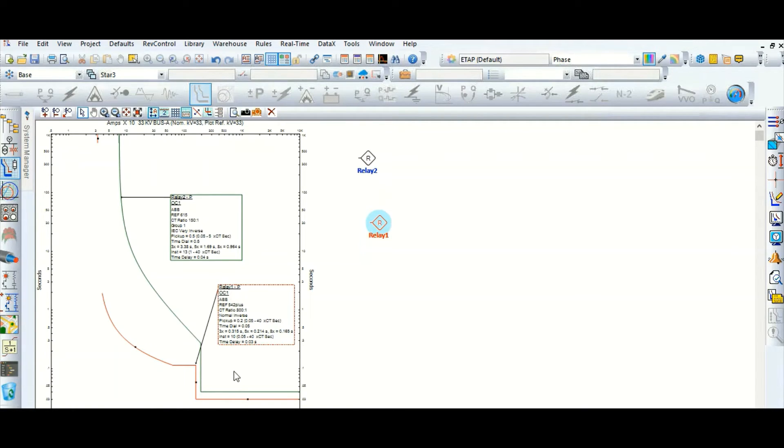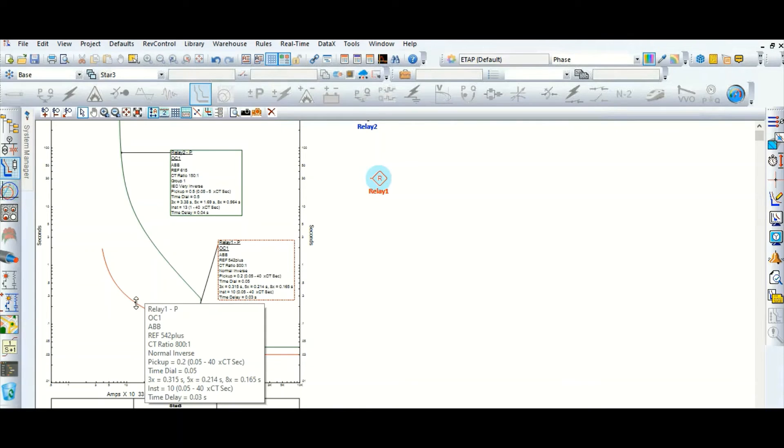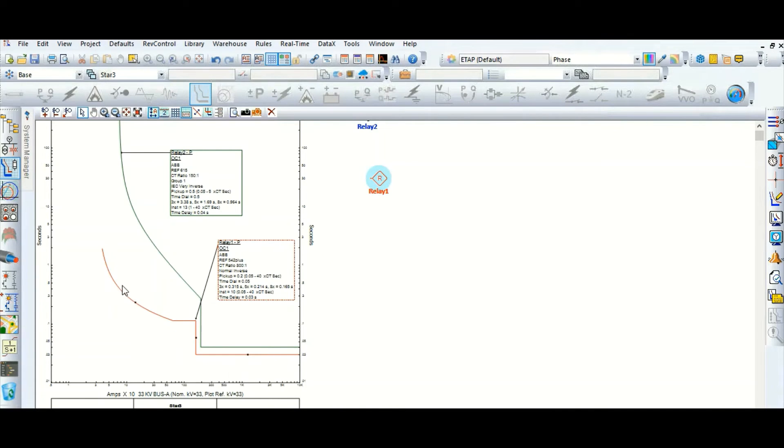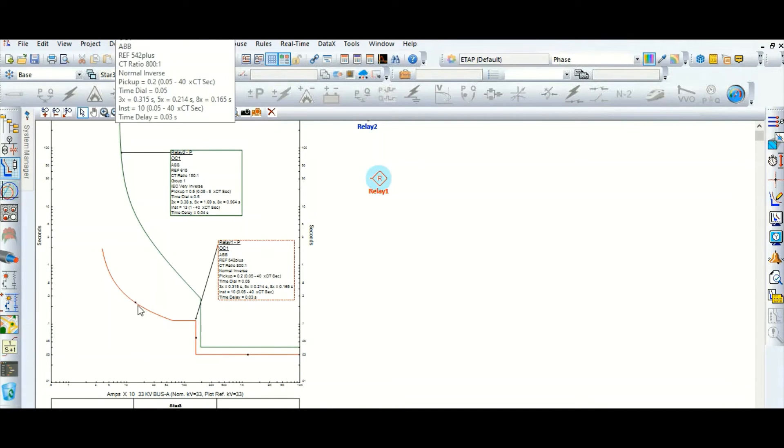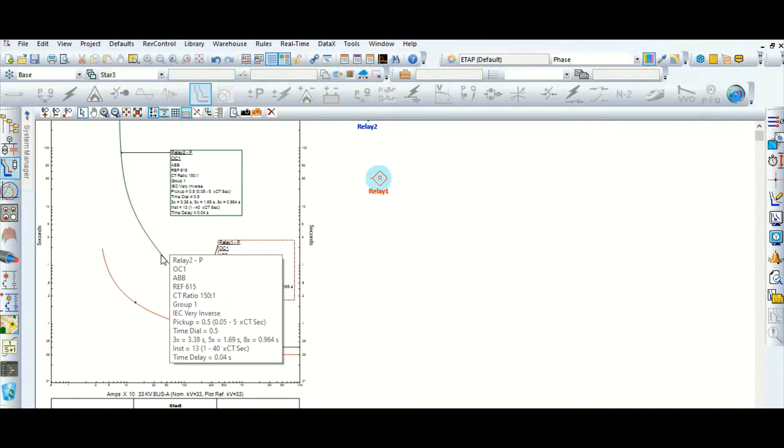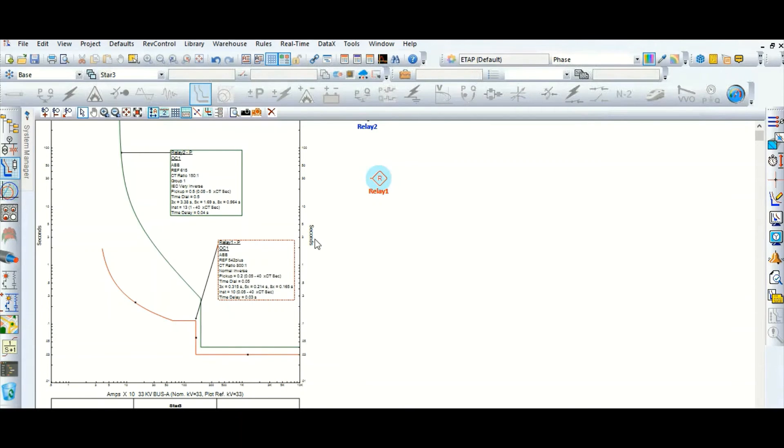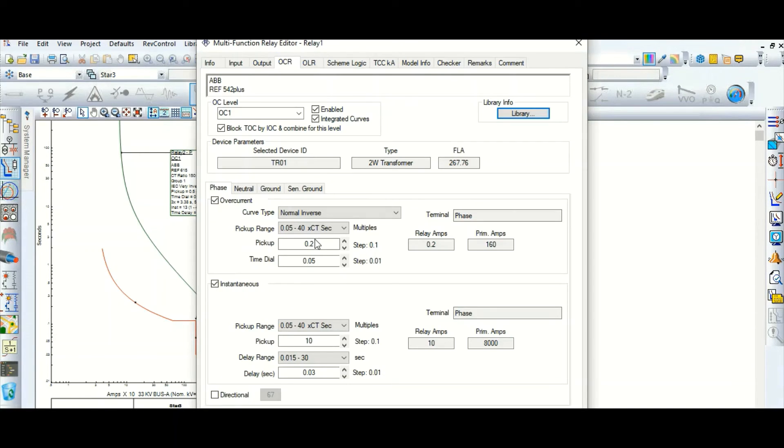But now the question will come, how much time coordination is there? Here we have selected the normal inverse curve and here we have selected very inverse in the transformer HV side. That's why this gap is too much. So if we change this curve type...